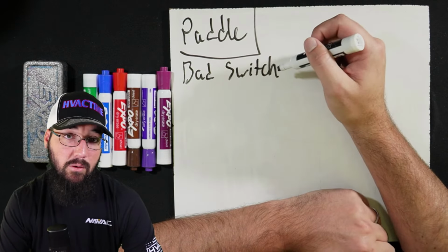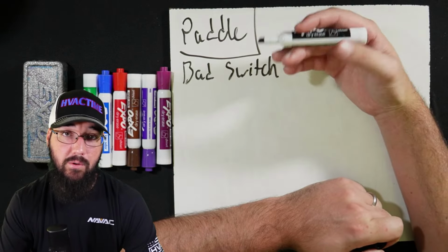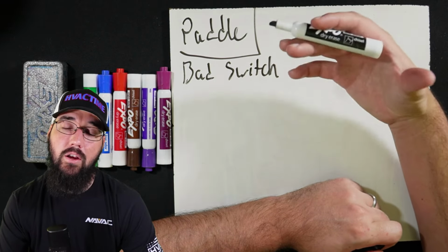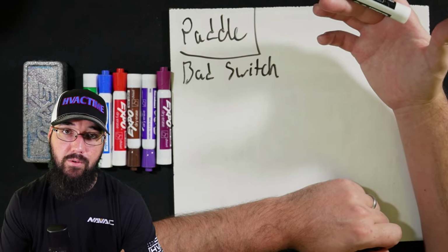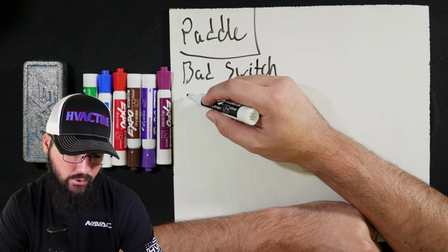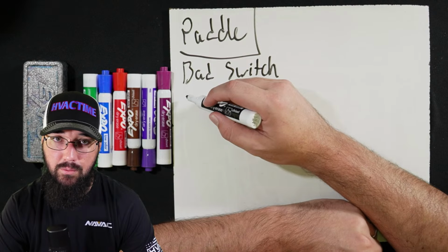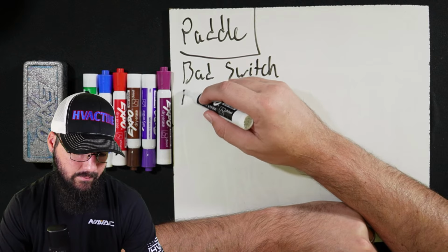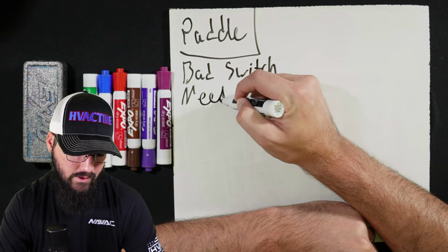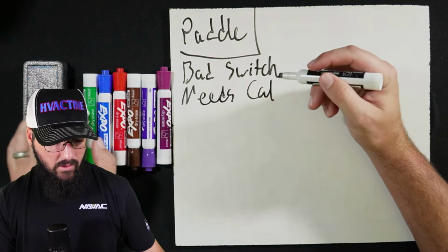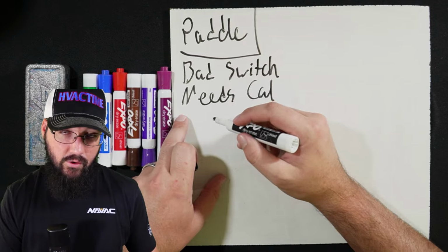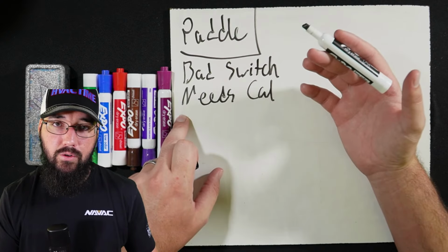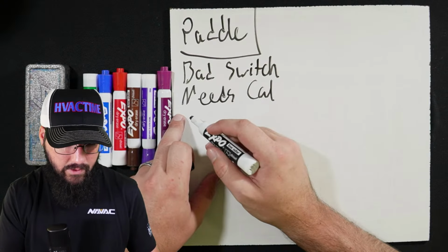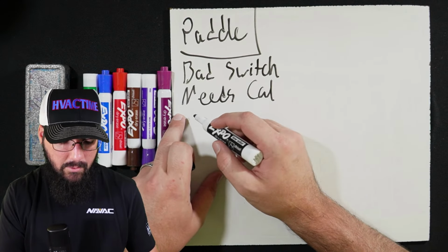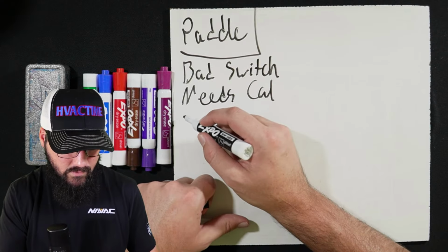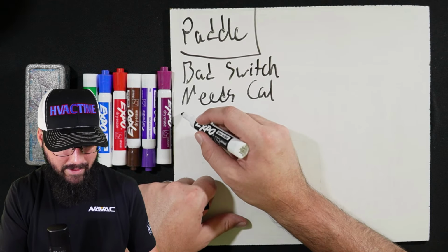It could be a calibration issue. Those paddle switches do have springs to adjust their sensitivity. People mess with them all the time. And so it could be just out of adjustment, so it needs to be calibrated. Needs cal. Especially if this is a newer switch, they may not have put enough paddles in. So it could be a paddle flex issue.